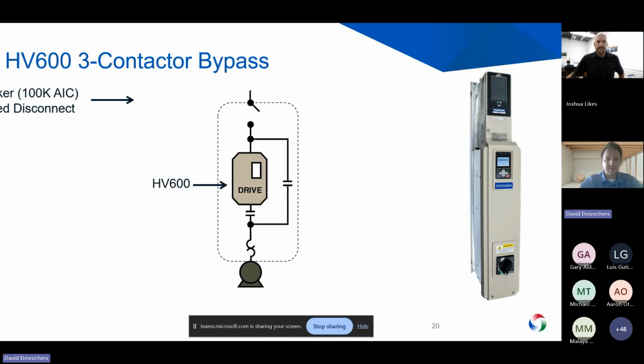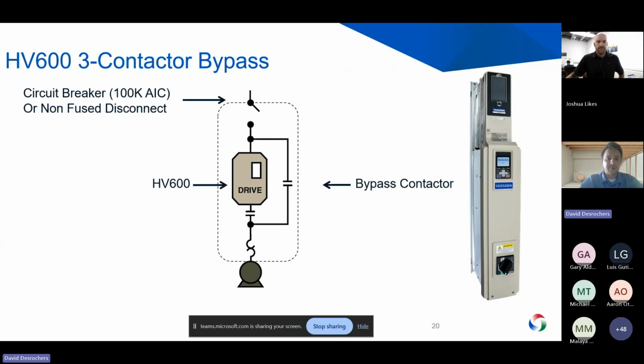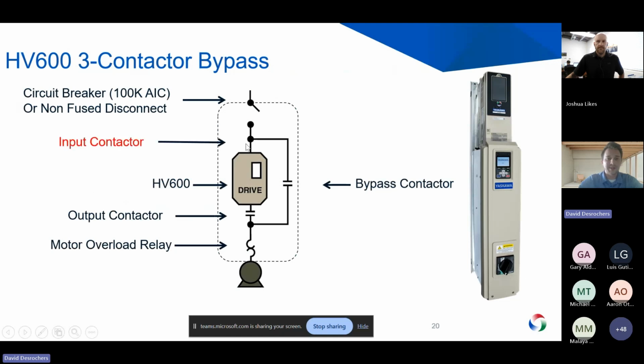And then finally, the last one would be the 3 contactor bypass. Again, just stick with me here, but imagine there's another contactor here. So we'd have 1, 2, 3 total. And this input contactor is very similar to the service switch in that it allows you to remove and connect power to the input of the drive whenever you like. And this is done electronically through the control in that bottom enclosure, like I was saying earlier.